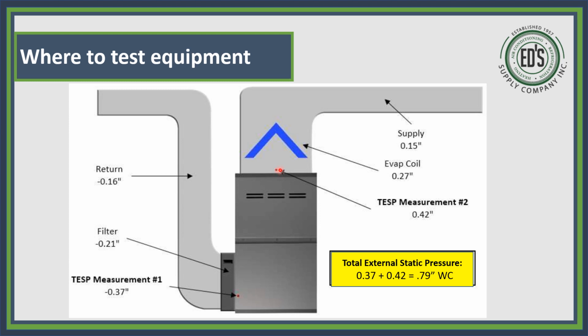If I'm going here, it would be during a heat session, okay, where this would not be equivalent unless it's dirty. But that's why I just check them up here, because it's usually easier. This is where the air is coming out of that, and I want to check right here and see if I've got a dirty coil or I've got resistance. And you'll be able to see that. See this number here, this is 0.42. Now, on a supply, you want to look at 0.3. This needs to be a 3. You'll see 3 up to maybe a 5. Keep that number in mind. On the return, this should be more like a 0.1 or a 0.2. When you get into 0.3s, you've got resistance and that return needs to be fixed.